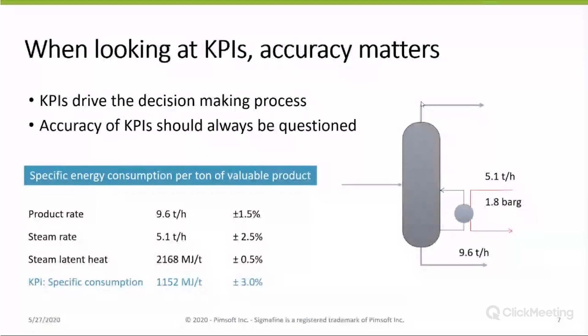Since we are using steam tables, which are very well tuned, the accuracy is quite high, so 0.5%. If we combine all this together, we can derive also the associated accuracy of the KPI, which ends up being plus or minus 3%—which is not a negligible number at all if you think of the value of a big energy consumer that you may have in your plant.